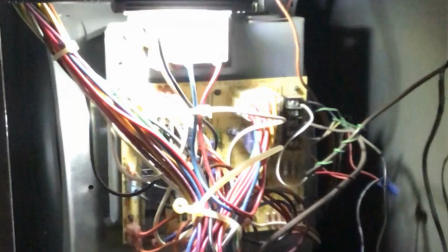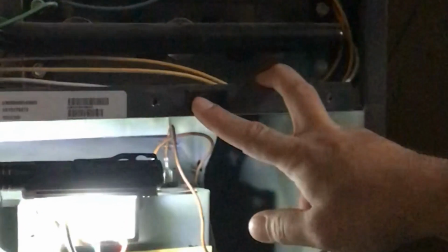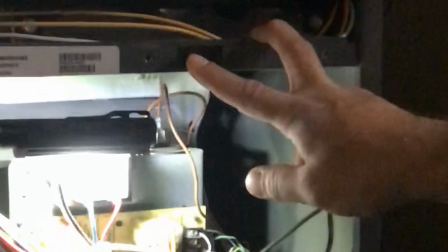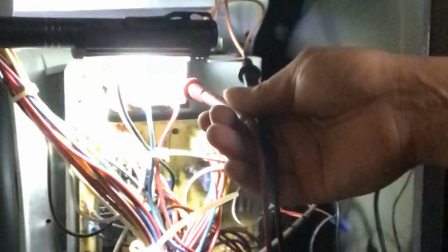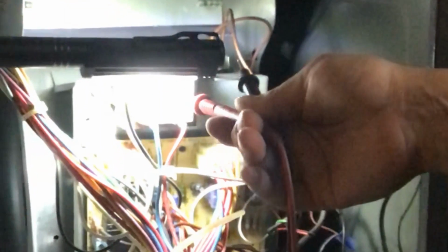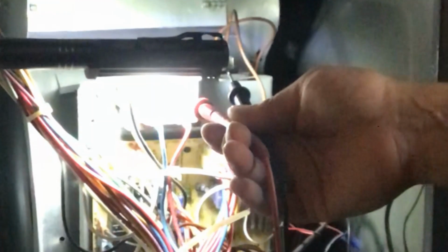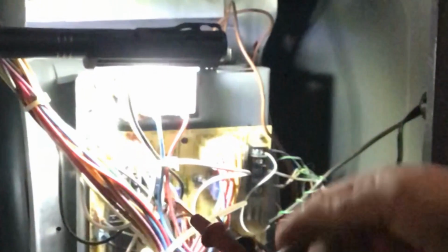How the furnace generates the 24 volts is you have a line coming in. The first thing it hits is the door switch. If the door switch is open, nothing's going to work. If the door switch is closed, everything should work. All right, so that's pretty simple. The next thing we're going to talk about is your transformer. What your transformer does, it has an input of 120 volts and an output of 24 volts. So everything that runs off 24 volts is supplied by the output of your transformer.